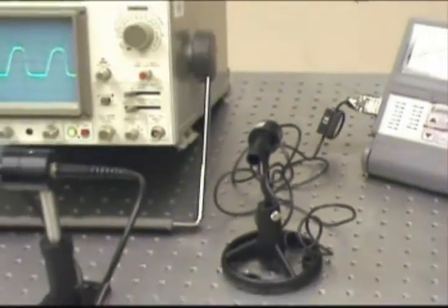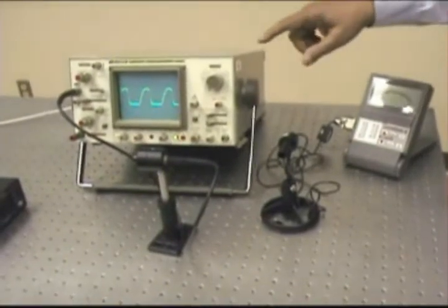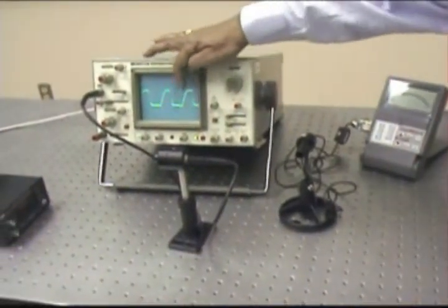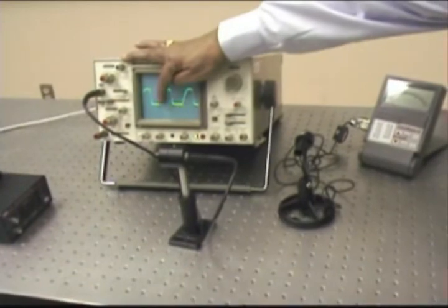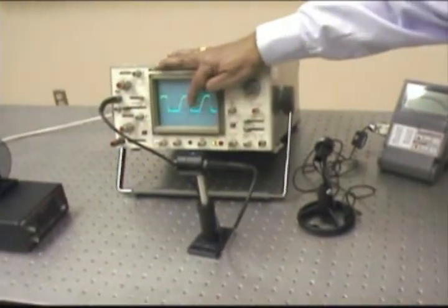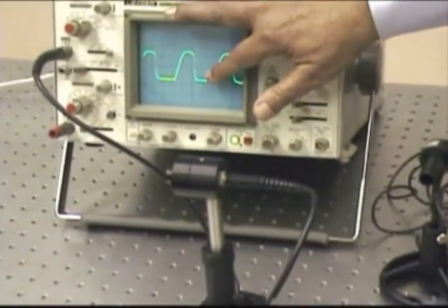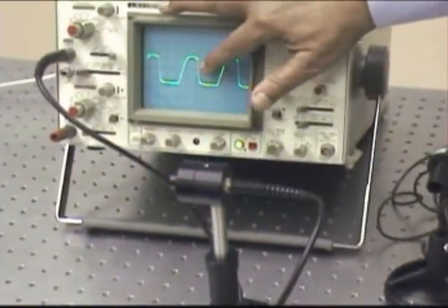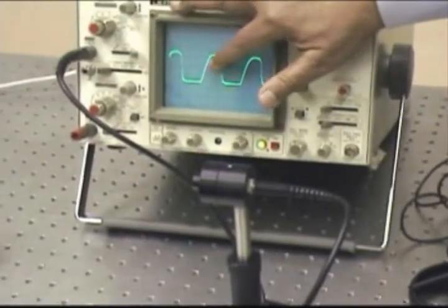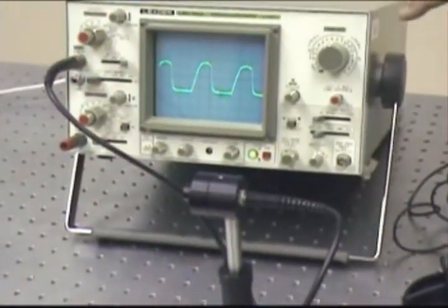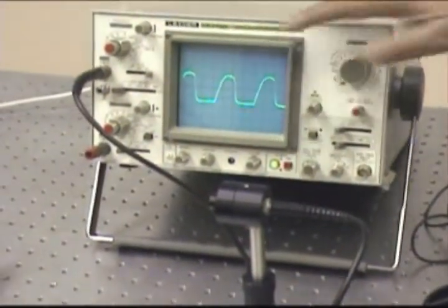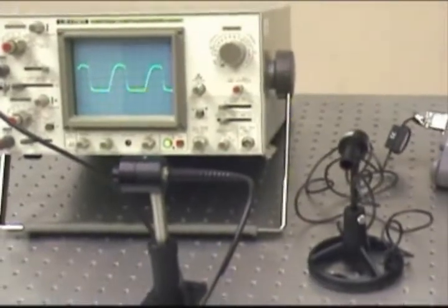Once we have finished measuring the pulse parameters, we can measure the pulse average. As you can easily see, there are 3 pulses shown here. If we measure from the beginning of this pulse to the beginning of the next pulse, that will give us the PRT. And we can adjust the height of this pulse also and measure the width in time, which is our delta T half, the full width at half maximum. So with these two and the P average, we can calculate all the parameters.